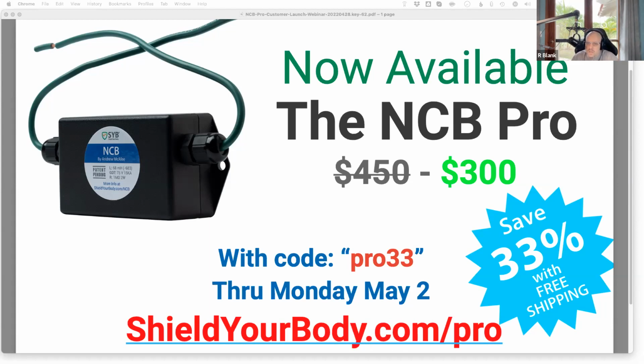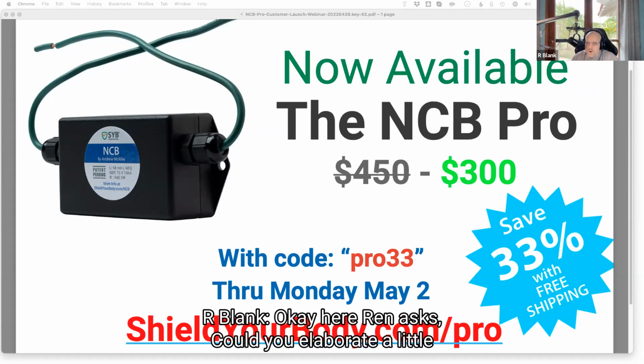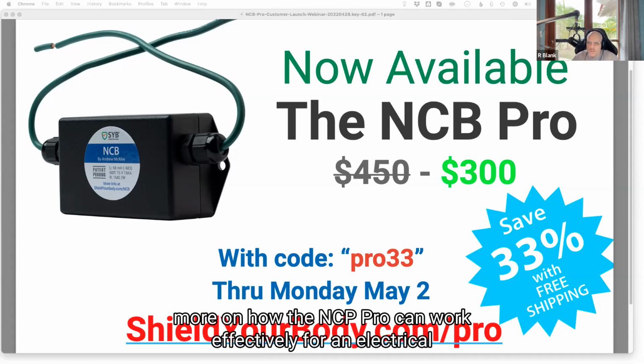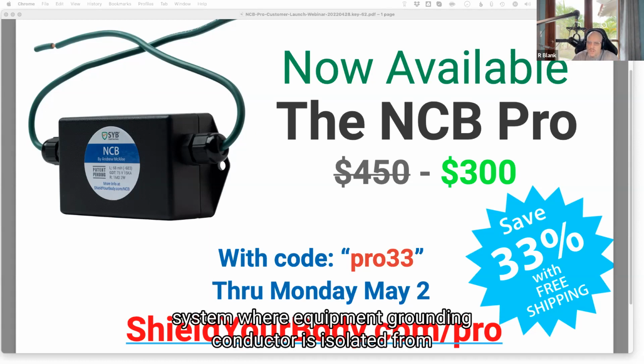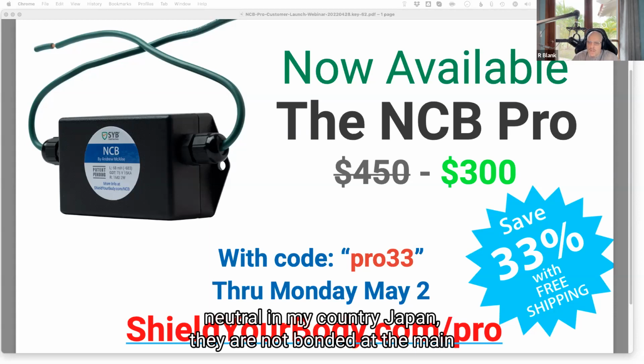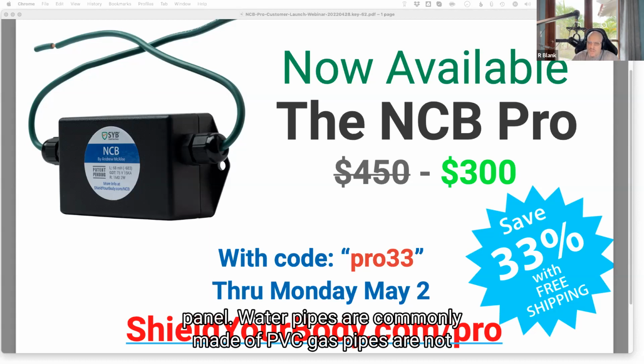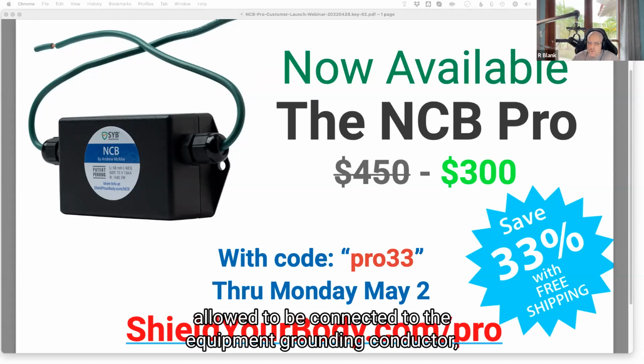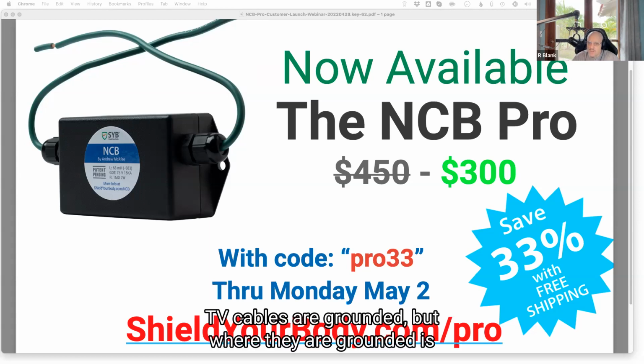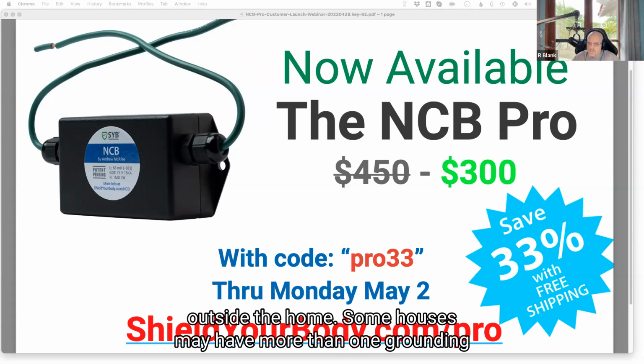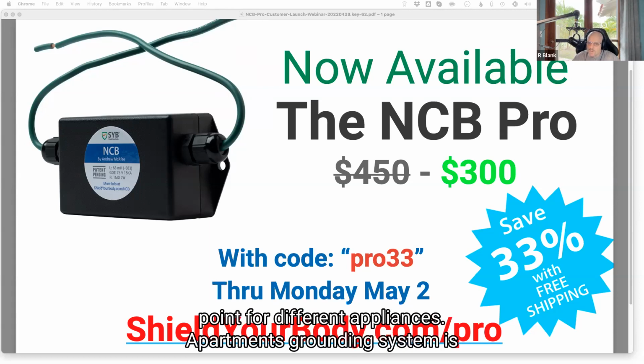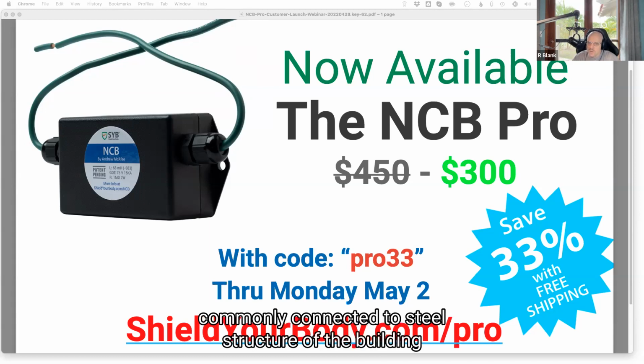Ren asks, could you elaborate on how the NCB Pro can work effectively for an electrical system where the equipment grounding conductor is isolated from neutral? In my country, Japan, they are not bonded at the main panel. Water pipes are commonly made of PVC. Gas pipes are not allowed to be connected to the equipment grounding conductor. TV cables are grounded, but where they are grounded is outside the home. Some houses may have more than one grounding point for different appliances, and apartments' grounding systems are commonly connected to the steel structure of the building.